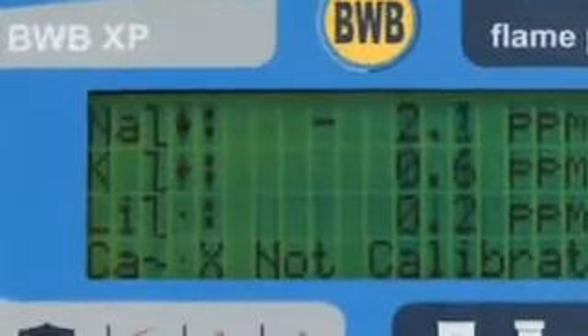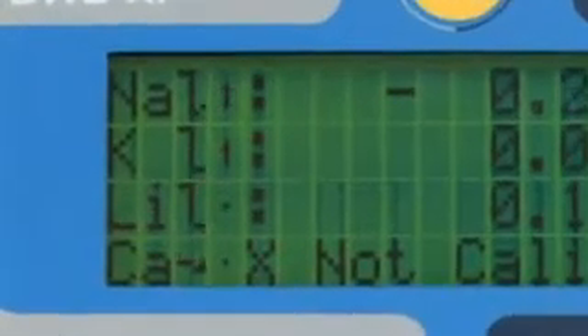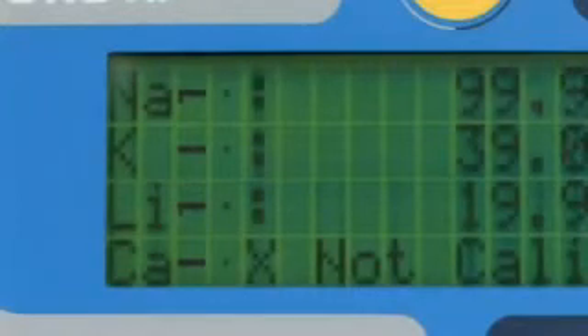Now go back to the Bwb Xp and take a reading. First of all, press the accept key or read shortcut key and then aspirate your sample. Be sure to monitor both the Bwb Xp and the FP-PC software to see when the readings, both numerical and graphical, have stabilised. When the readings are stable, press the Take Reading button. Retrieve the report by ticking the last button.